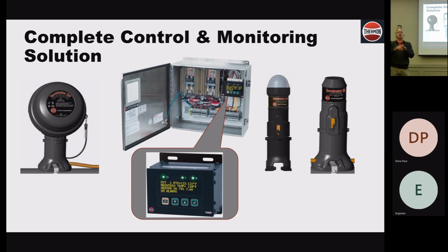But so yes, it's always better to have controls, and it's always better to modulate that as opposed to not modulating it. From an energy consumption standpoint, primarily, it's not going to hurt the trace. You're not going to have rapid fluctuations in power. So if you go to a light switch and you flick it rapidly, are you going to exhaust the lights a little bit more? Yes, you will. If you do that to heat trace, you're going to exhaust that heat trace a little bit quicker. But that's not what we're discussing, right? You're looking at a very slow thermal inertia. So there's no worries there at all.